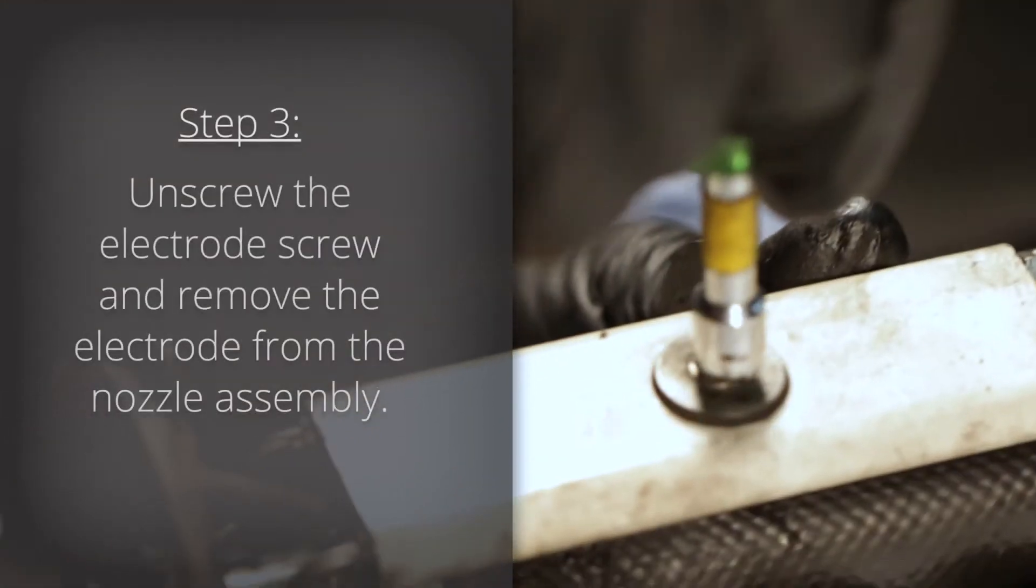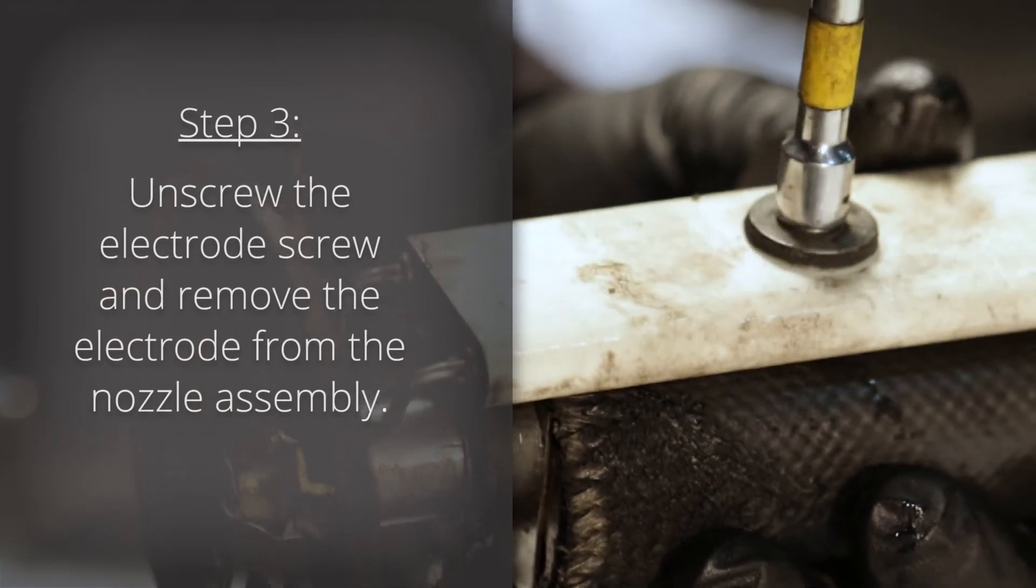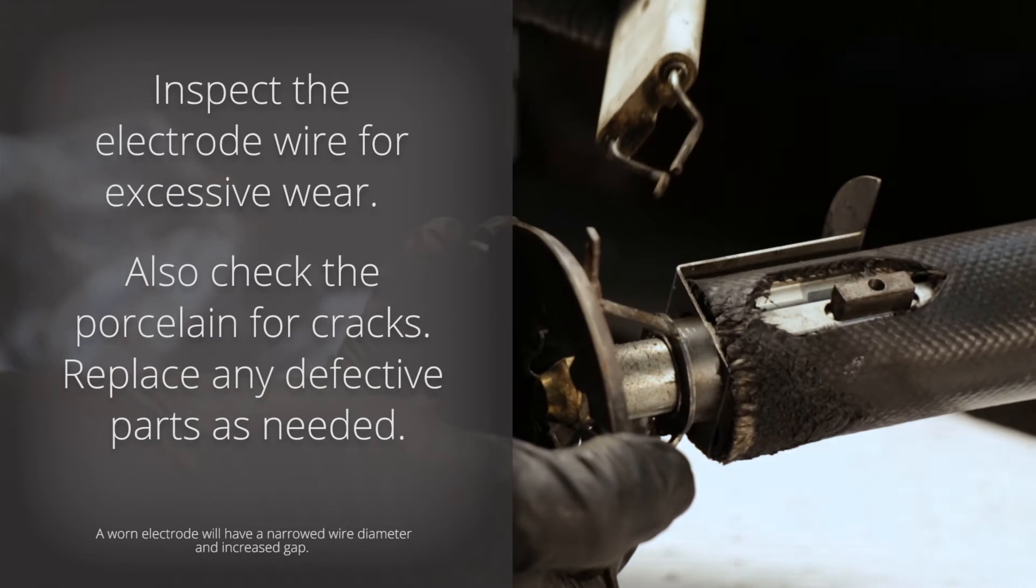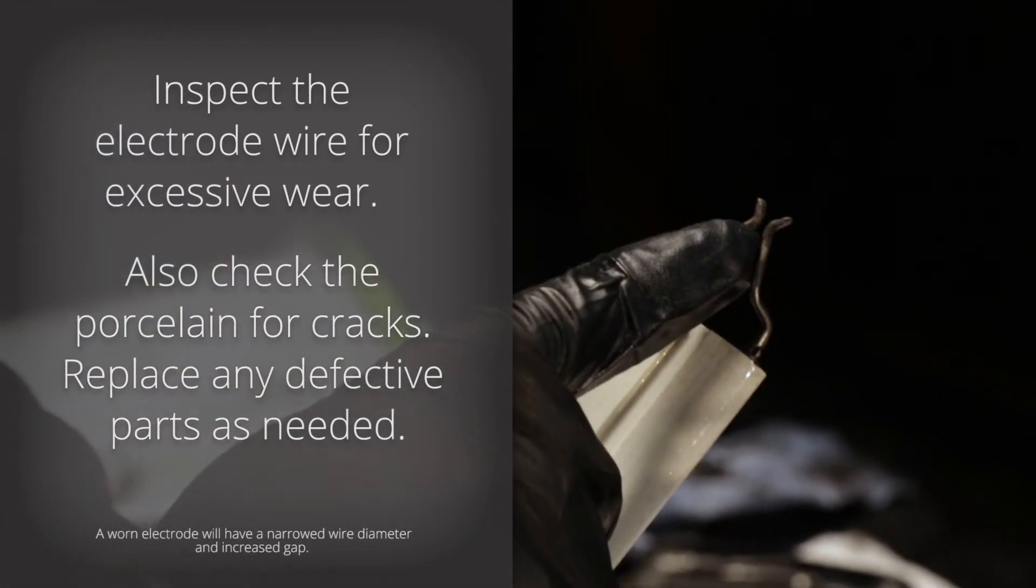Step 3. Unscrew the electrode screw and remove the electrode from the nozzle assembly. Inspect the electrode wire for excessive wear. Also check the porcelain for cracks. Replace any defective parts as needed.